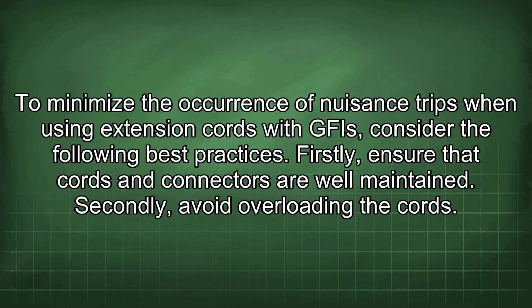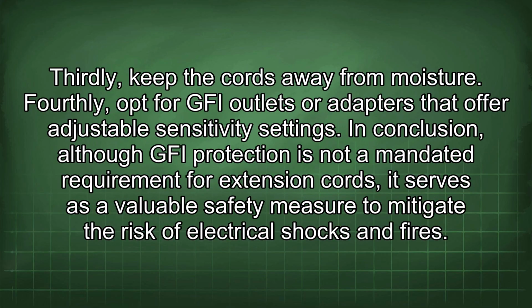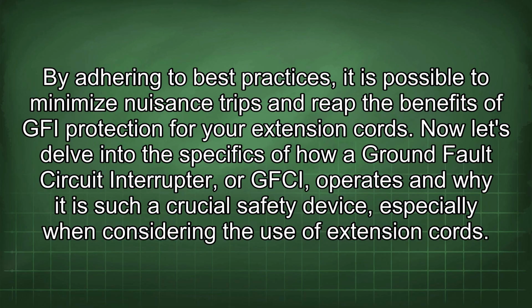To minimize the occurrence of nuisance trips when using extension cords with GFI, consider the following best practices. Firstly, ensure that cords and connectors are well maintained. Secondly, avoid overloading the cords. Thirdly, keep the cords away from moisture. Fourthly, opt for GFI outlets or adapters that offer adjustable sensitivity settings. In conclusion, although GFI protection is not a mandated requirement for extension cords, it serves as a valuable safety measure to mitigate the risk of electrical shocks and fires. By adhering to best practices, it is possible to minimize nuisance trips and reap the benefits of GFI protection for your extension cords.